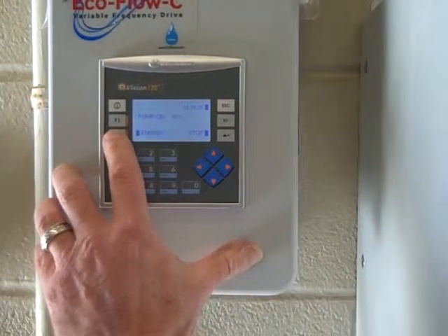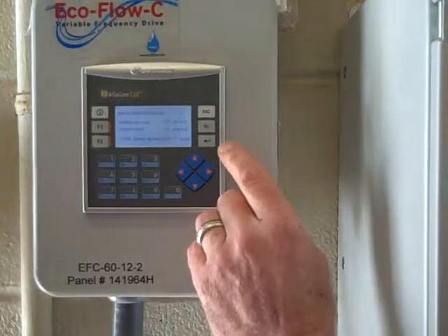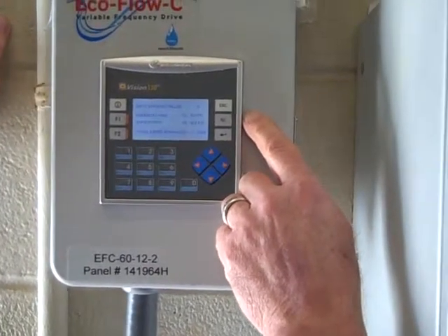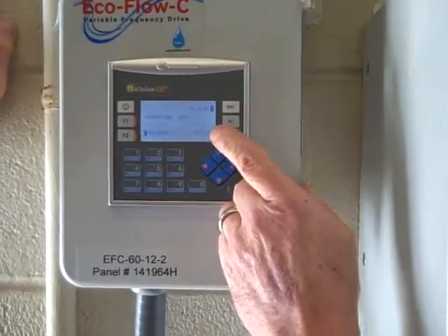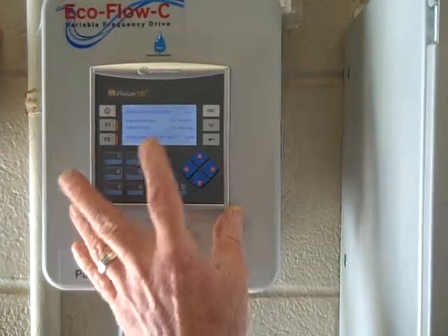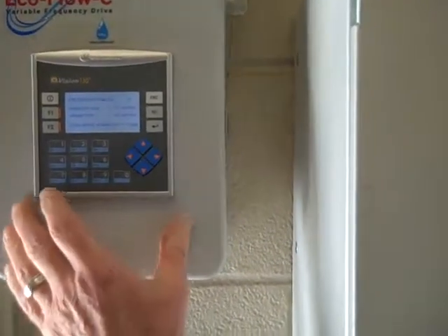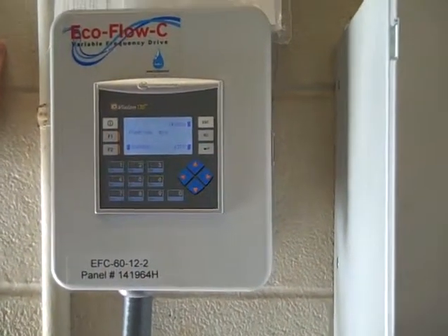The energy screen, what we did when we started up is we logged how many kilowatts this thing pulls, and it'll time out in about 15 seconds before we push it. 13.910 kilowatts at full power, running at 60 hertz. Right now you're using 10.416 kilowatts, so roughly 3.5 kilowatt savings every hour, okay? Let that thing time back out. And it has a 0 here, it'll calculate it, so you'll have a running total of how many kilowatts you've saved from install.